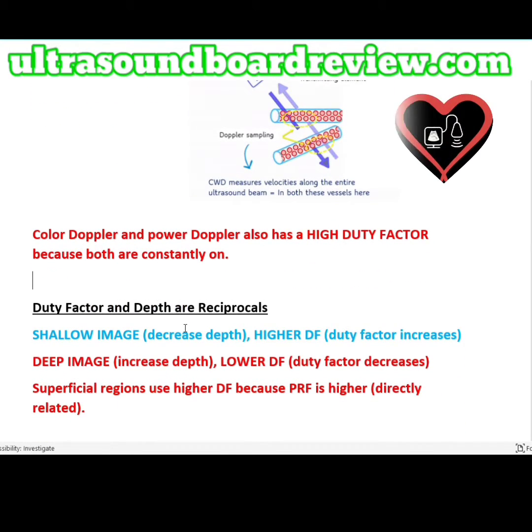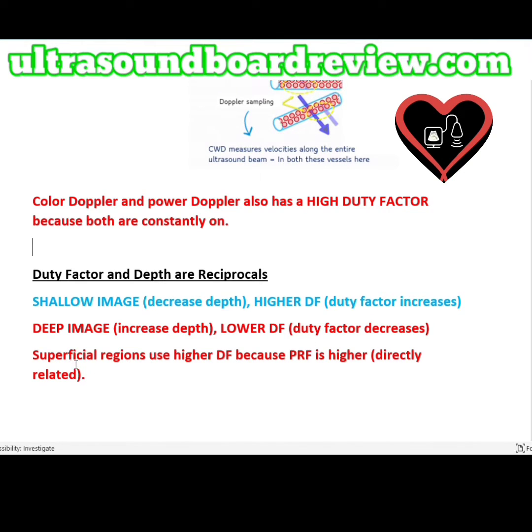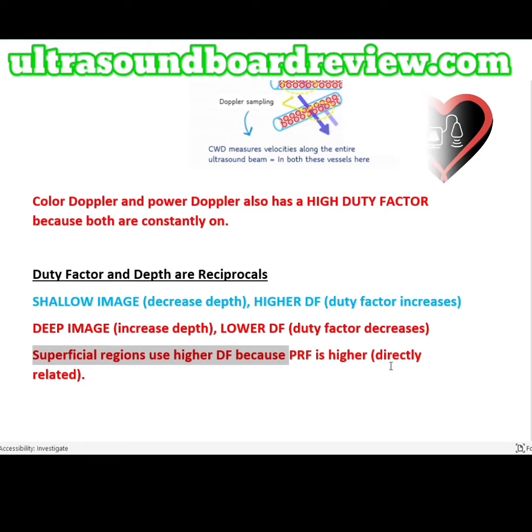When you compare duty factor and depth, they are reciprocals of each other. That means when you image at shallower depths you will have a higher duty factor, and when you image deeper your duty factor will decrease. The reason superficial regions have a higher duty factor is because your PRF is high, which is directly related.